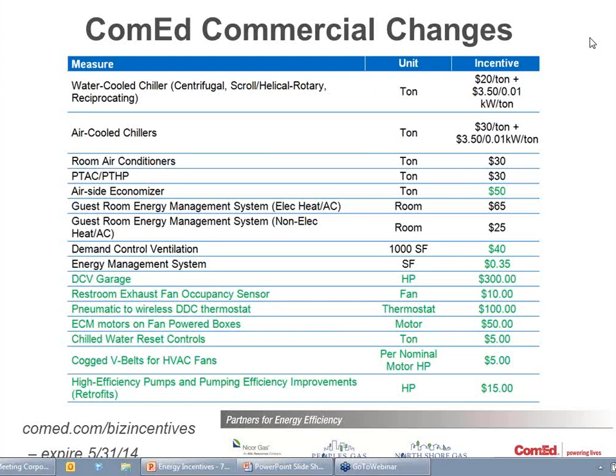So there's a few other ones on there. There's one on here, ECM motors on fan power boxes. I've gotten that call several times already. And there is a rebate for it, and you can do it, and it's $50. But it's not just getting the ECM motor on the fan power box, which is available on almost any manufacturer's fan power box. You actually have to change the building automation system's control sequence to modulate the speed of the fan. That's not a normal DDC sequence. You have to come up with and create a sequence to do that. So I would be very cautious on that.